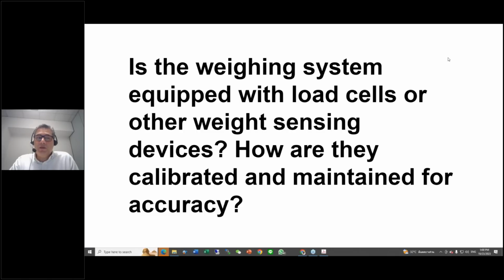How to calibrate the load cell? There is a procedure that our technician does during the equipment startup and the training of the local team. We supply certified mass together with the equipment, and according to a wizard on the specific load cell, we add it to make the calibration and to give the linearity to the system and to the load cell.